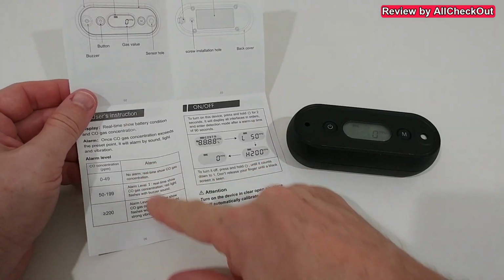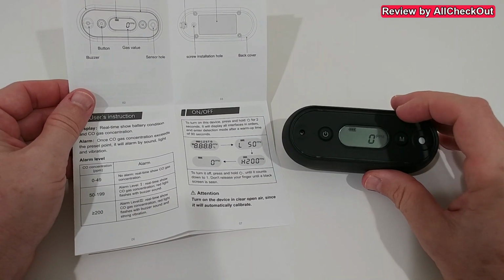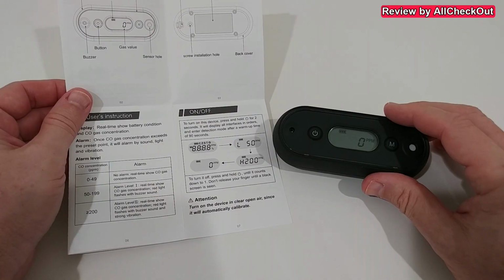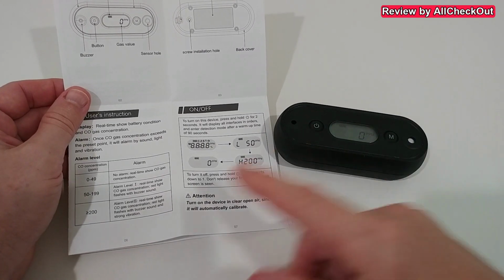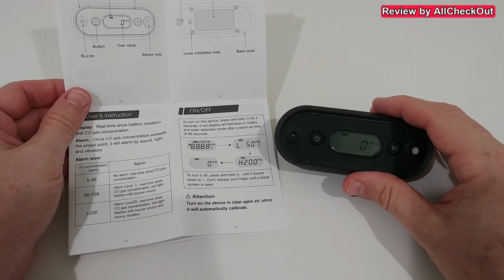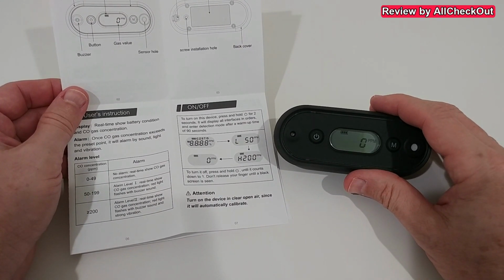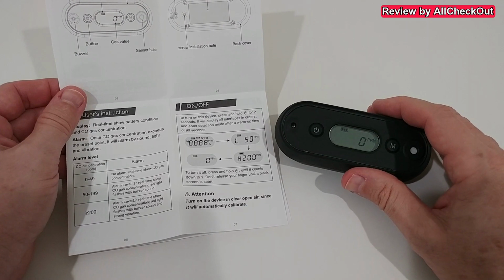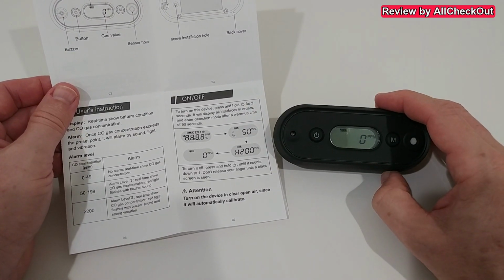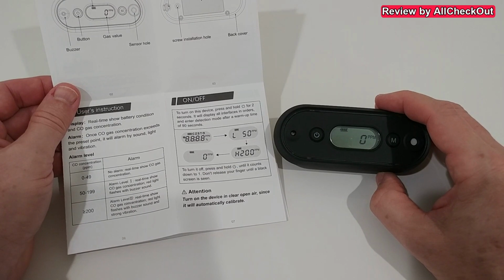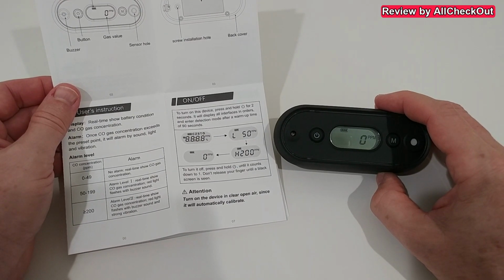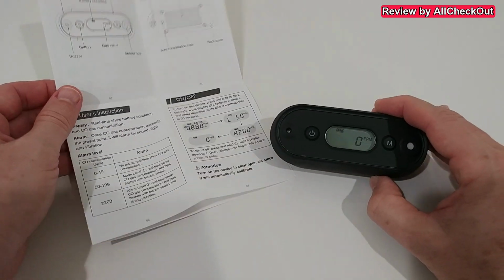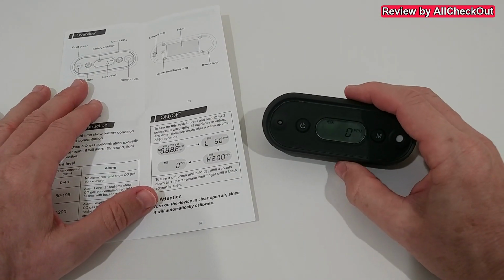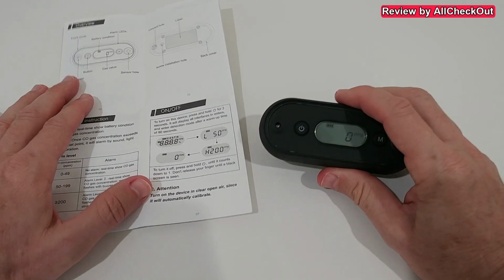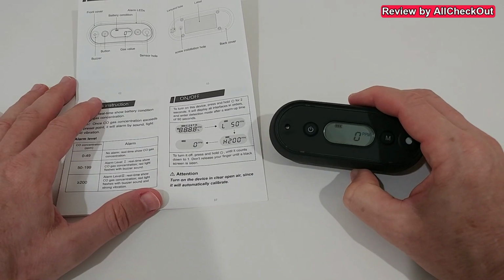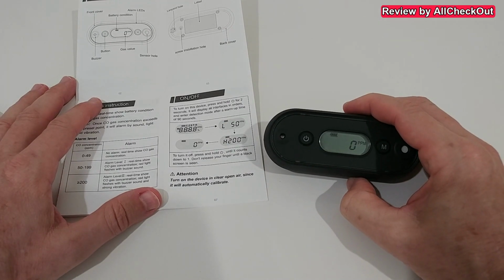What's also very important to know is that we have 3 levels. From 0 to 49 ppm, it's not doing anything because it's considering this as a normal number. From 50 to 199, this is alarm level 1. We'll see a red light flashing and hear a buzzer sound. And for everything above 200 ppm, that's alarm level 2. Then we will see the red light flashing with the buzzer sound and even a strong vibration. So we have 3 different types of alarms. That's something which is awesome. So it's almost impossible to not realize when something is wrong as long as you're using this device and it's turned on.